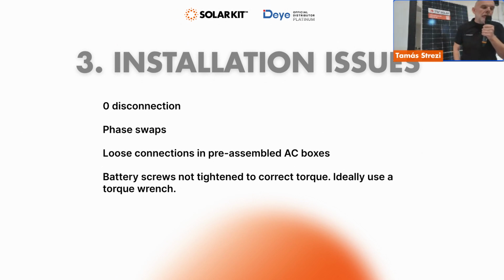So the null was floating, and the inverter kind of shut off as soon as you applied any household loads to it. It was really interesting, because that state actually pulled the null towards the active phase. So the voltage towards other phases made the grid connections fail, because there was 90 volts between one phase and null, and there were 350 volts between null and the other phases. So really interesting problem, but one-off.